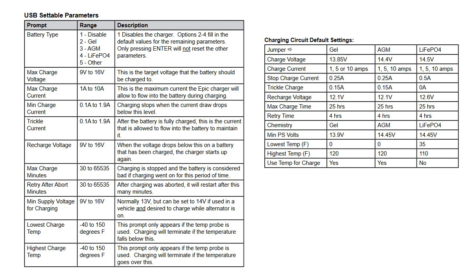The charge current is limited by the max charge current and min charge current values. Notice that the max charge current can only go up to 10 amps. Trickle current is the current used to maintain a charged battery. Recharge voltage tells the charger when to start up again. Charging will stop once it reaches the max charge minutes. Retry after abort minutes tells the charger when to restart if charging was aborted.